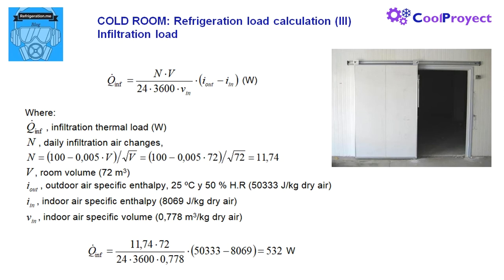Other parameters we have to consider are specific enthalpy and volume of the indoor and outdoor air. Specific enthalpy is the sensible and latent energy intrinsic to the air in joules per kilogram of dry air. The specific volume is the opposite of density, in cubic meters per kilogram of dry air. We can check these characteristic values in a psychrometric chart for moist air.